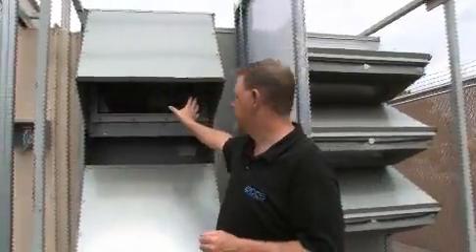So this is the outside. This is where we exchange the air. So what you can see here is two pieces. This is actually the exhaust air. The air temperature out of the back of a server that we have in there is about 126 degrees Fahrenheit. The hot air is sucked up to the ceiling. It comes across the ductwork and actually just exhausts 100% of the air.